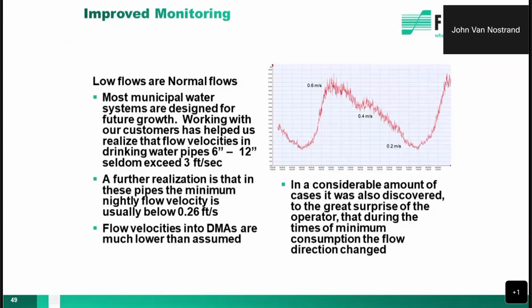So the other thing I'd like to point out is that we assist a lot of water utilities, and we've learned that most drinking water piping systems flow below 3 feet per second. Why is 3 feet per second important? Because again, that's where the magmeter starts to perform the best. Will it read below 3 feet per second? Sure. But it drops off the accuracy.